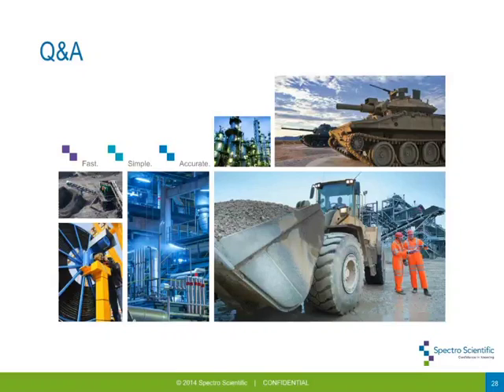Do these devices produce a report or provide a USB connection for uploading data? Yes — several of these systems have an onboard interface where, for instance on the FluidScan, you have an onboard computer that saves data on a database. Almost all these technologies have complementary software loaded on a PC, and then using a standard USB cable, you can synchronize your database and then export or review that data on your PC.